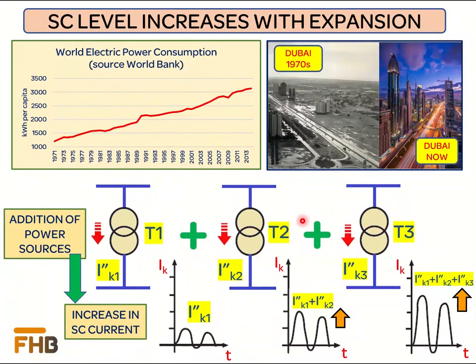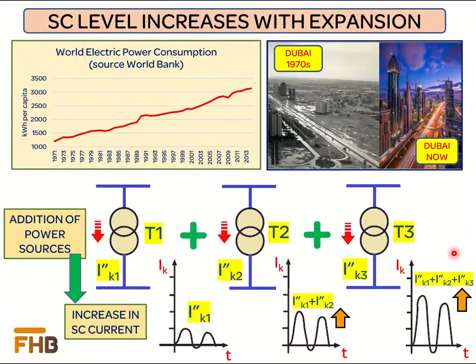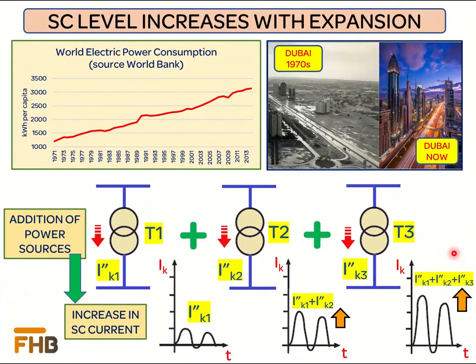We can feel lucky if the increase in short circuit level stays within the rated values of the installed equipment. However, what if the value of short circuit current exceeds beyond the rated value? The electrodynamic forces caused by this new value of short circuit current will destroy the insufficiently dimensioned electrical equipment. Are we going to replace the electrical equipment by increasing the system voltage or by increasing the rated short circuit current of the installation? The answer will be no, as it involves a huge amount of investment cost.